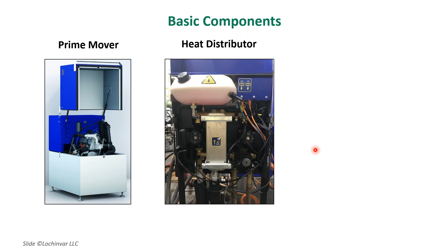On the right-hand side, these are the connections going to the stratification tank, which has another pump and an actuator, and the control box will actually control the speed of the motors in order to optimize heat transfer between the two systems. It begins to learn the system, learns the hot water usage, and will work accordingly to provide the maximum amount of heat for the domestic hot water.